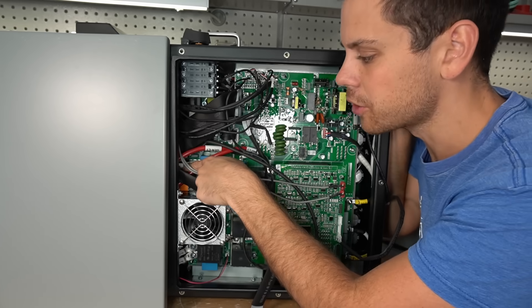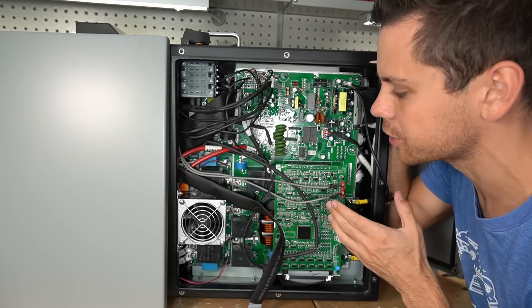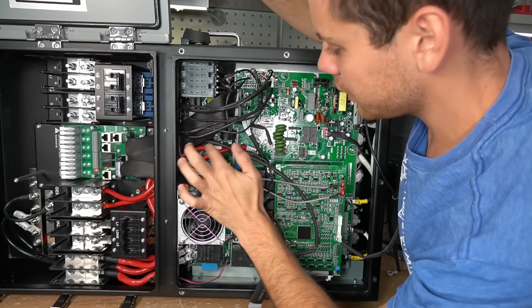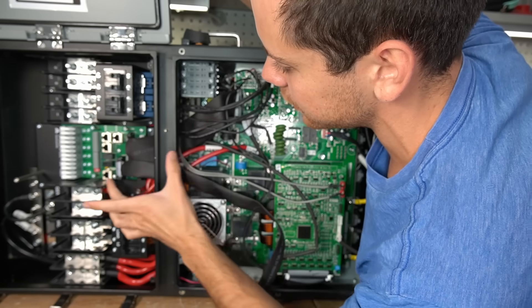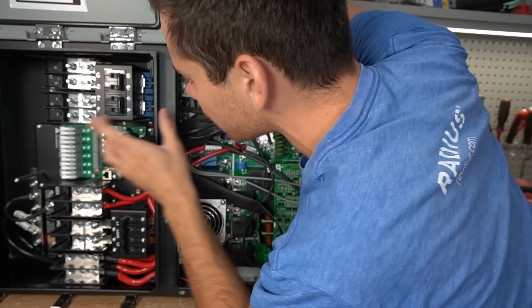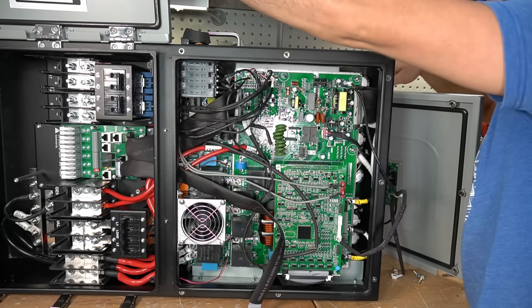The conductors have hydraulic crimps, which is very nice to see. The boards have labels everywhere identifying what everything is, so it's easy to work on if something fails — you just follow the wires to a label and know exactly what you're working with, and you can verify all connections are tight. There are more boards on the back of this side, and a lot is packed into this thing along with the cooling system.